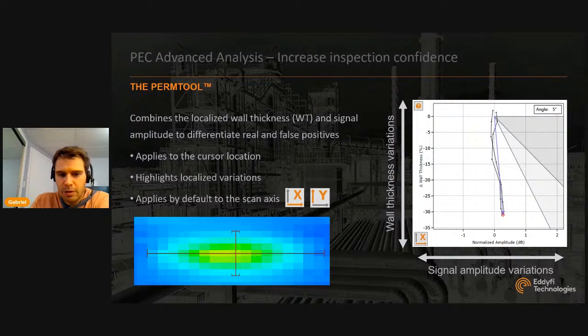So the PERM tool is a local tool. It's not a filter or something that's going to eliminate a false positive entirely, but it's a tool where you can put your cursor over an indication and apply the tool on one of the two axes. By default, the tool is going to be applied to the scan axis where you have the highest resolution typically. And we're going to draw a point for every single pixel in that C-scan, for every single A-scan, basically.